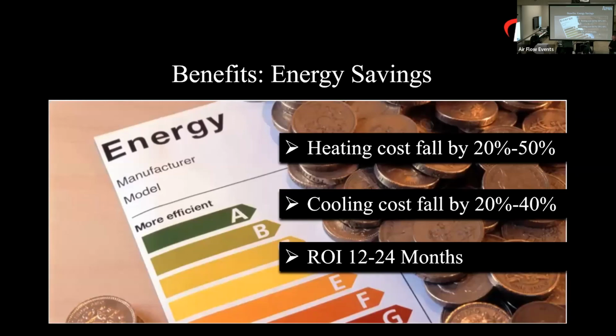And what happened in Australia is their rooftop units cost about three times the cost of the ones here in the US. And so they look for alternative cooling down there. They look for evaporative cooling through fans. They'll go into a particular project and say, hey, we can't afford the rooftop units. What can you do? So our branch in Sydney will go in and talk to them. And these are some of the reports coming back from Australia, talking about their cooling costs falling by 20 to 40% by what they're doing down there. So it's kind of interesting.